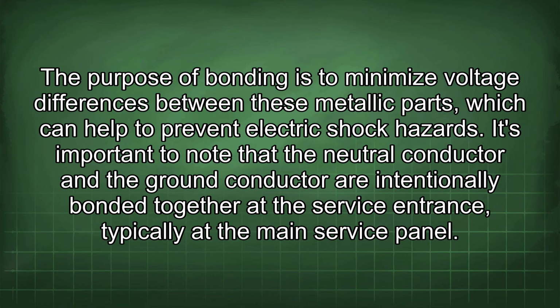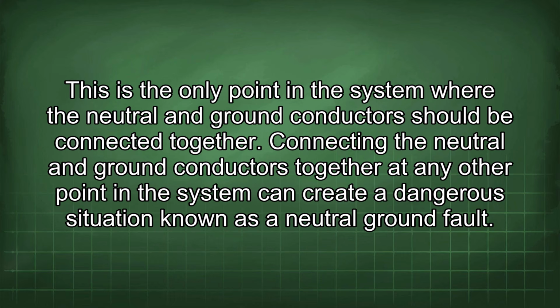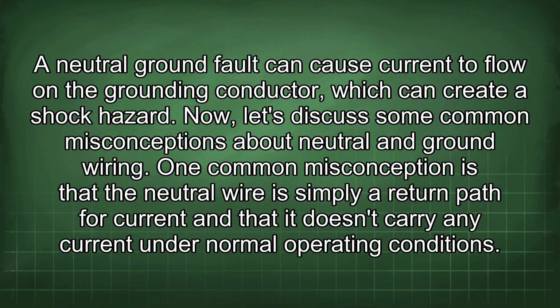It's important to note that the neutral conductor and the ground conductor are intentionally bonded together at the service entrance, typically at the main service panel. This is the only point in the system where the neutral and ground conductors should be connected together. Connecting the neutral and ground conductors together at any other point in the system can create a dangerous situation known as a neutral ground fault. A neutral ground fault can cause current to flow on the grounding conductor, which can create a shock hazard.